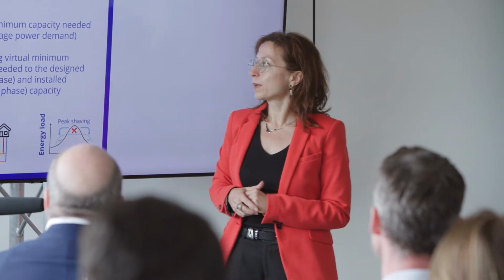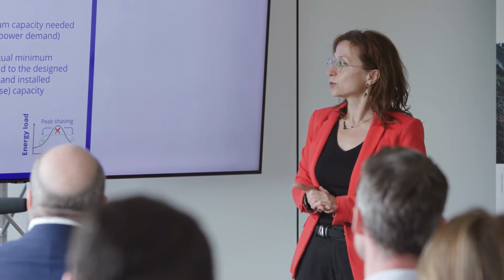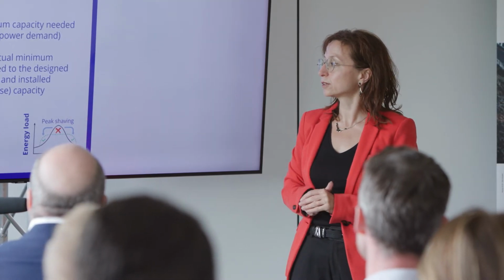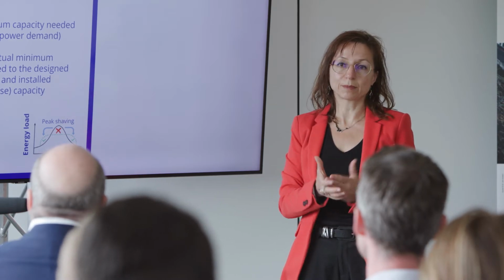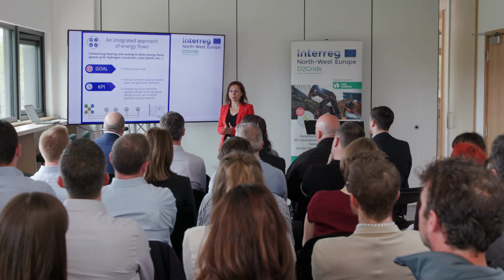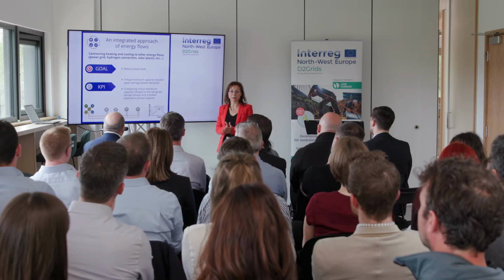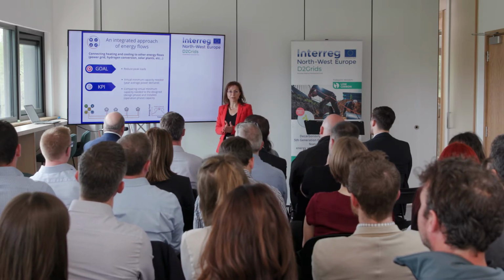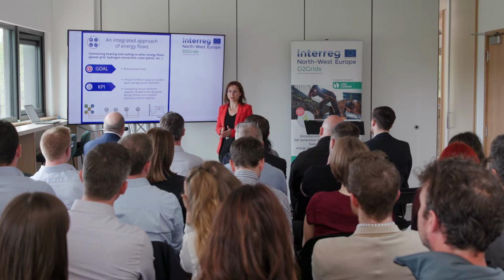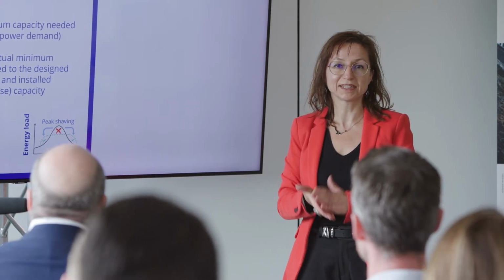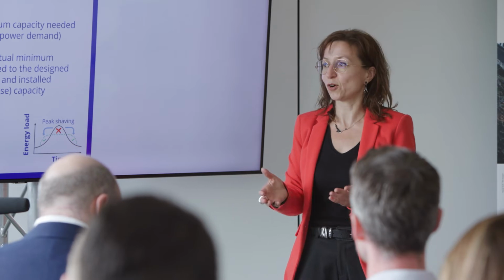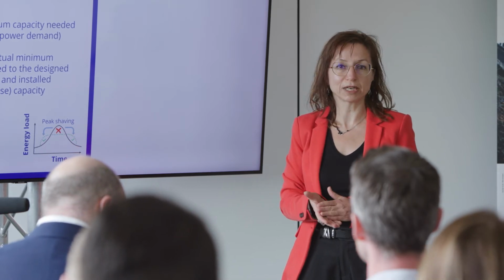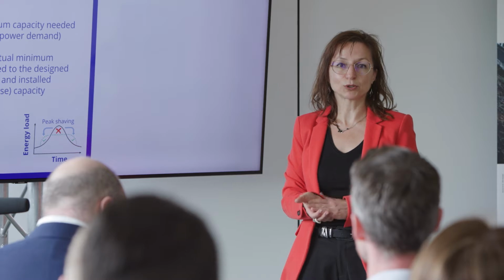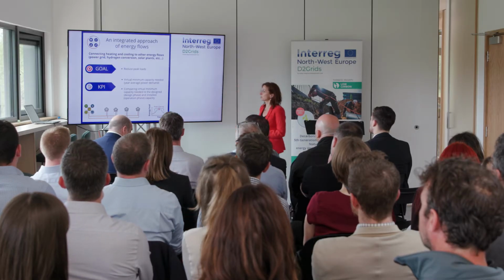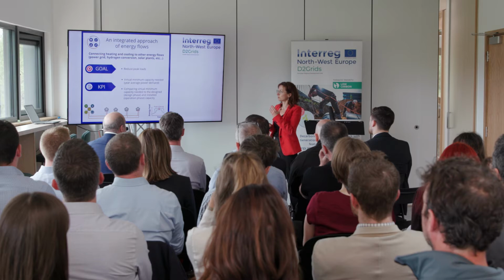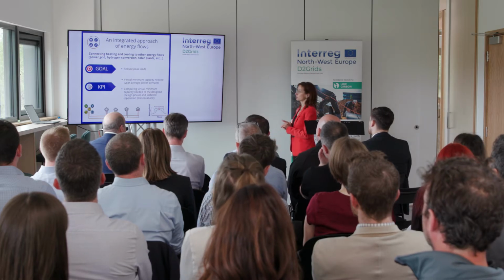We also try to compare the virtual minimum capacity needed at the design phase to the installed capacity in operation. As mentioned, everything has to do with over-dimensioning. A lot of district heating and cooling networks are over-dimensioned because they account for the worst case scenario, the coldest day. But the coldest day, with its lowest temperatures, occurs only a few days or hours, so it may not be worth dimensioning your network for this period. Instead, try to keep it as low as possible and use the energy exchanges in your network.